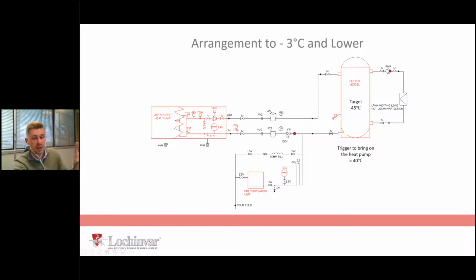Now, it looks quite simple as a schematic. It is. That schematic is basically what you would expect to see for a heat pump doing heating. Now, interestingly as well, you can see I've got an electric heat pump serving a buffer vessel. Couple reasons for that. Reason number one, for every kilowatt of air source heat pump you have on a system, you can probably expect to see about 10 litres of thermal storage. Generally, you do that through a thermal store. So the heat pump, I said 50 kilowatts, that's going to be a 500 litre thermal store.